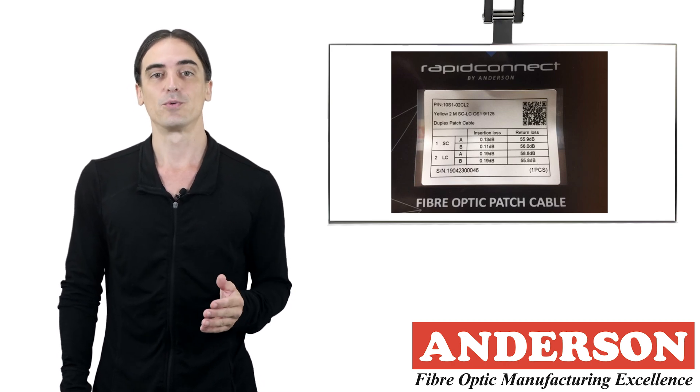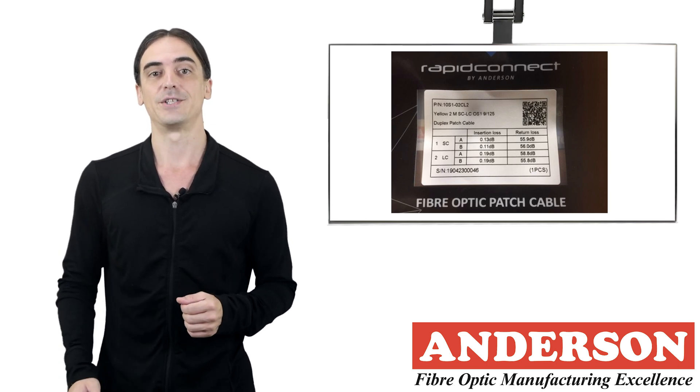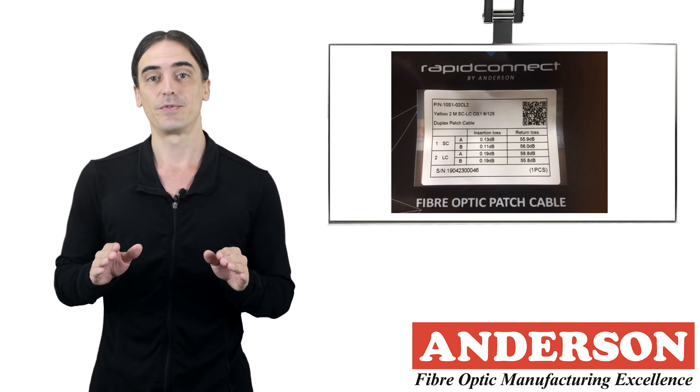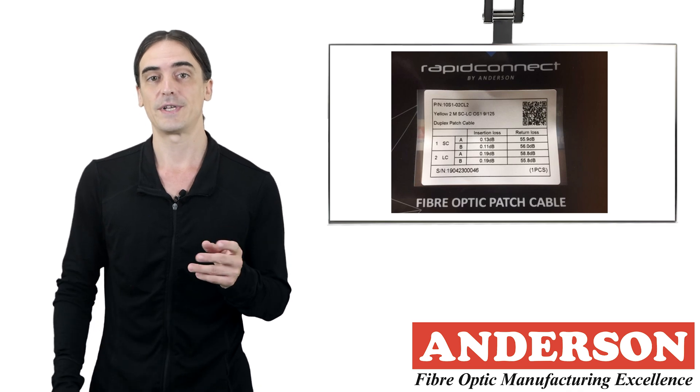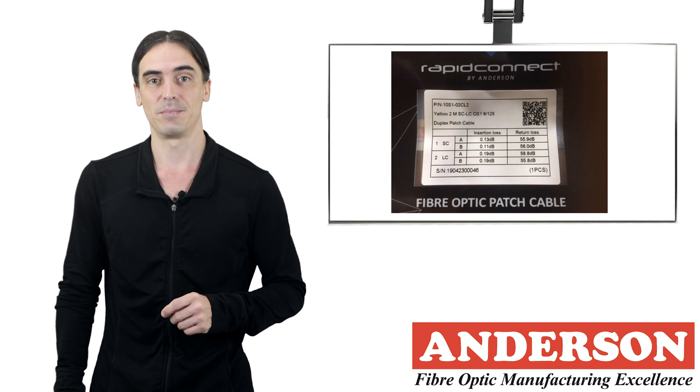Fiber optic patch cables will come with loss results, and these results will be listed on packaging. They should be tested in both directions, so there should be four test results for a duplex cable or two results for a simplex cable.